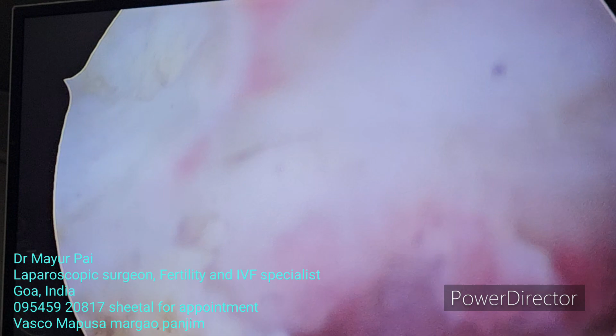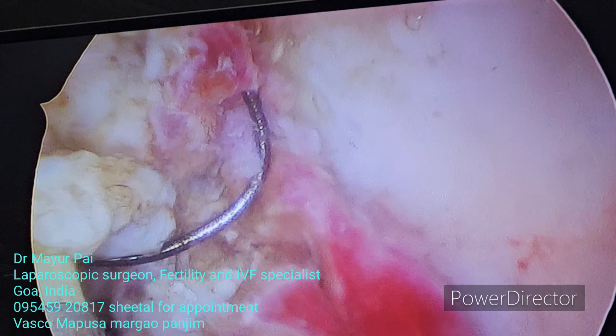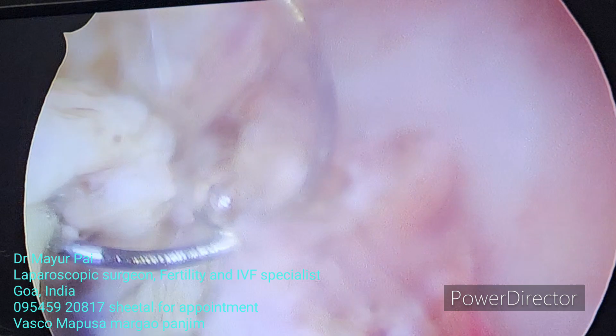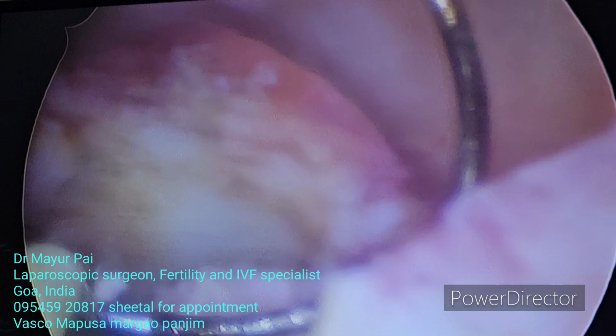So again, a lot of these bubbles, flush them out. These bubbles, remember, are made of steam. This steam is because of the water which is turned to steam, the water from the saline distension medium. Here short bursts are done. Here again we are breaking another rule of resectoscopy, I would say. We do not usually push the loop, we always pull the loop, but sometimes it is difficult.